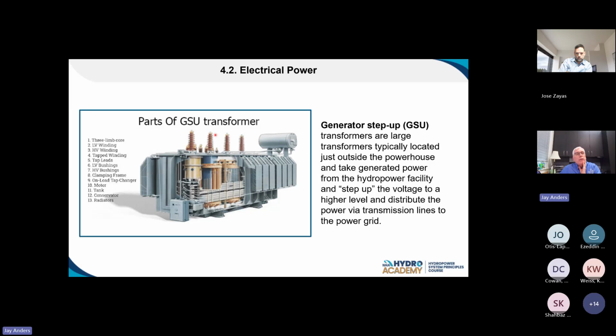That allows me to have a very high voltage going out to the grid. At the same time, I'm able to lower my current. As that current goes down, I have less resistive losses. We call it I squared R. Power equals I, we square it, and multiply it by the resistance of my transmission line.